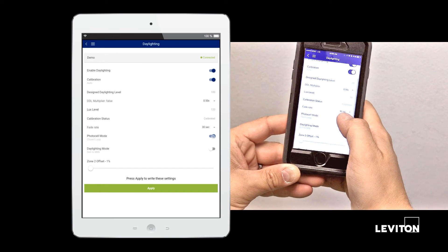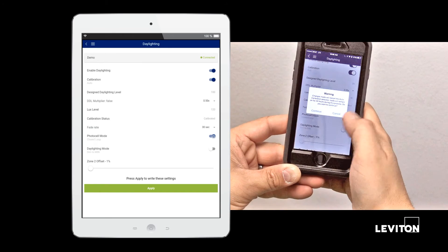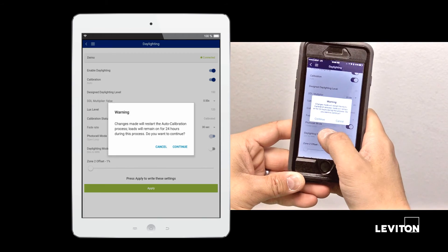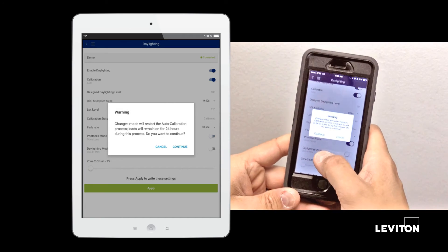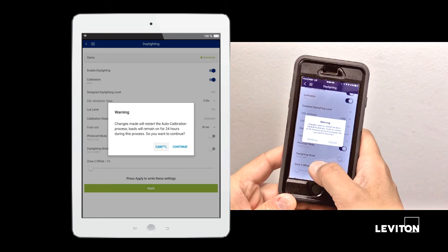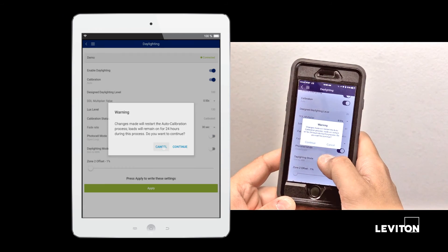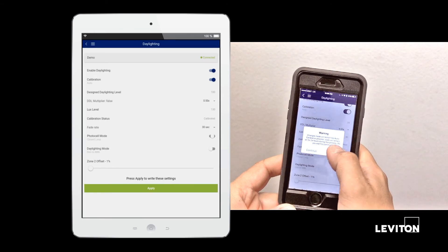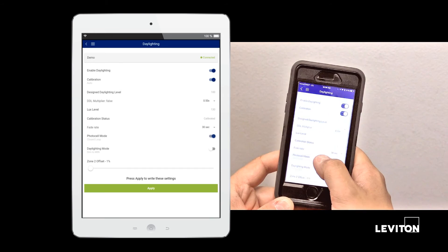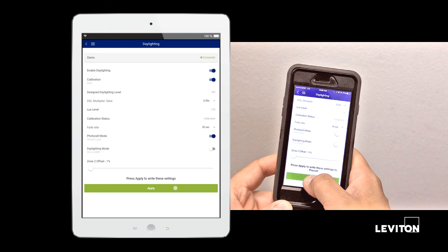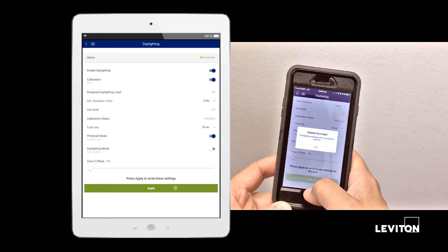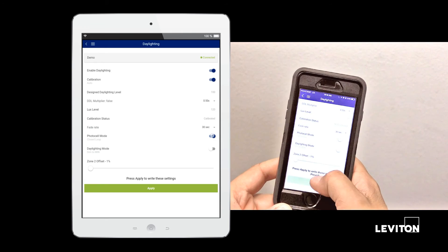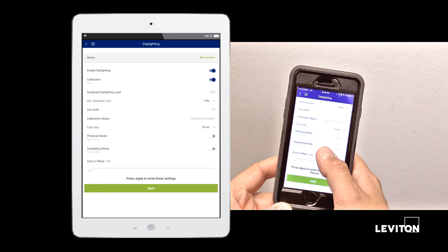Changing the photocell mode while in auto calibration will restart the auto calibration process, which is why we should do that before we start that process. And again, once you have made any changes on the daylighting screen, click apply to save those changes.